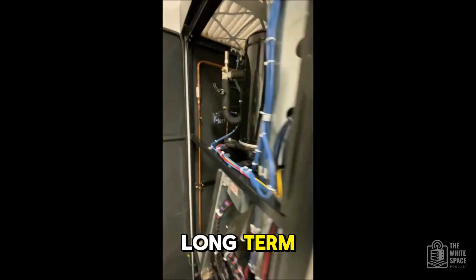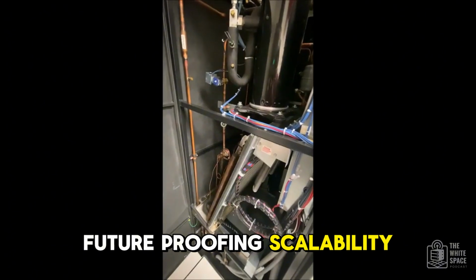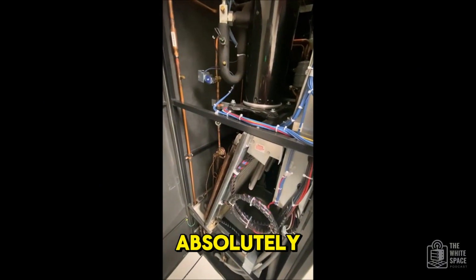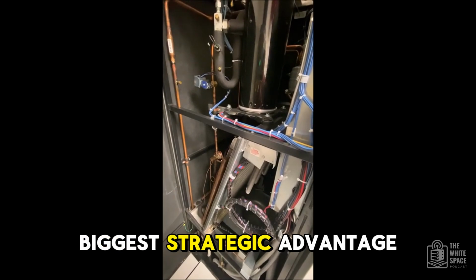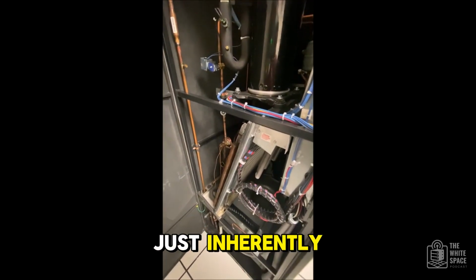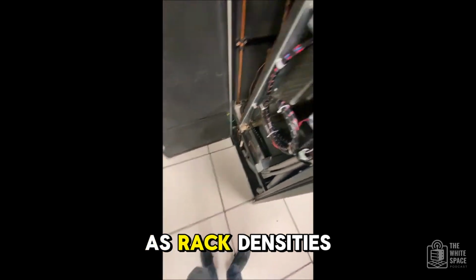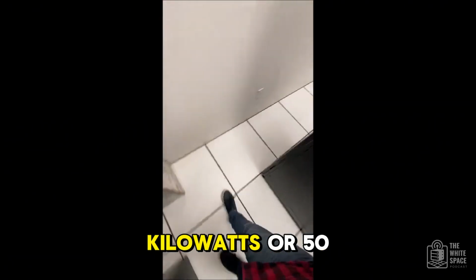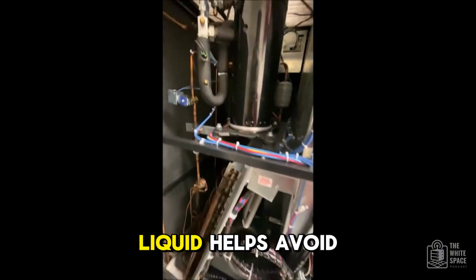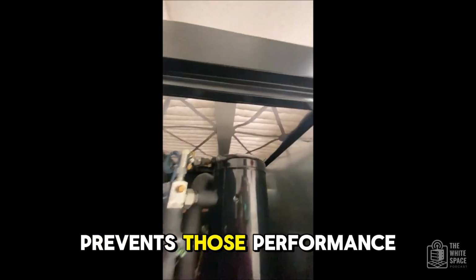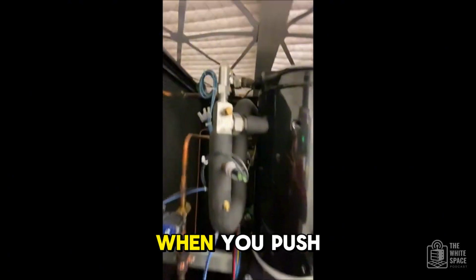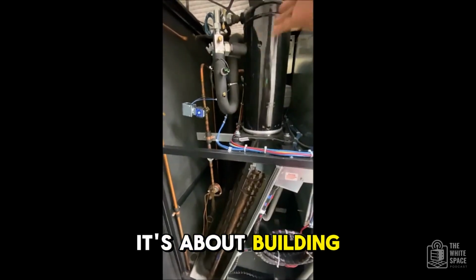So liquid cooling could still be the better option, even in a cold climate, depending on the workload. And thinking long-term, future-proofing, scalability. This seems like liquid cooling's home turf. Absolutely. That's arguably its biggest strategic advantage. Liquid cooling is just inherently better equipped to handle the future. As rack densities keep climbing, pushing past 30 kilowatts or 50 kilowatts, even higher for AI clusters, liquid cooling can scale to meet that demand. Air cooling often can't without massive infrastructure upgrades. Liquid helps avoid straining the power grid, prevents those performance throttling issues or outages when you push hardware to its limits. It's about building a data center that can handle tomorrow's workloads, not just today's.